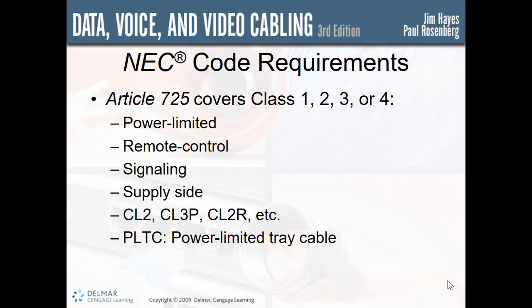Which brings us into codes. The NEC, Article 725, covers Class 1, 2, 3, or 4 remote control, signaling, and power limited circuits. The article can be very confusing, so if you don't understand the circuits designated as Class 1, 2, 3, or 4, what you need to understand is these are power limited circuits, or what we call signaling circuits. Every circuit covered in 1, 2, 3, or 4, some of them are power limited and some of them are signaling circuits.